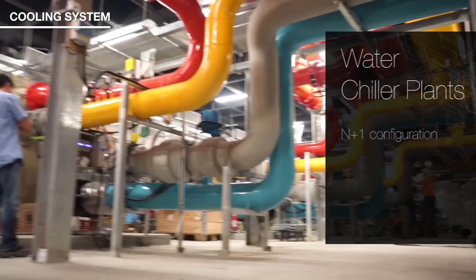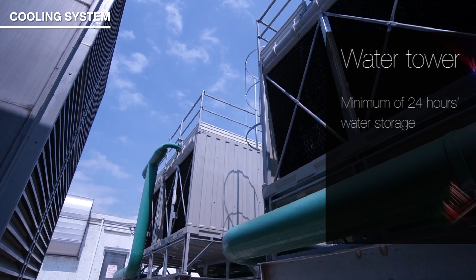Water-cooled chiller plants are configured with dual headers. Dual chilled water and condenser water pumps with independent valve controls keep plants running separately and provide a reliable solution in the event of mechanical or electrical hitches. All CRAC units are configured with ambient temperature maintained at 22 ± 2 Celsius and relative humidity kept at 55% ± 10%. Installation of CRAC units and chillers followed N+1 configuration, providing redundancy of 30% and 40% respectively, supported by 24-hour water storage. Cooling system power supply is supported by dual transformers and generators to prevent interruption.